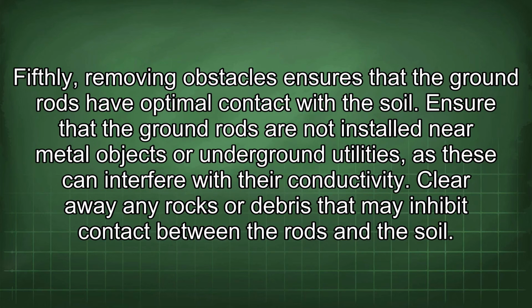Fifthly, removing obstacles ensures that the ground rods have optimal contact with the soil. Ensure that the ground rods are not installed near metal objects or underground utilities, as these can interfere with their conductivity. Clear away any rocks or debris that may inhibit contact between the rods and the soil.